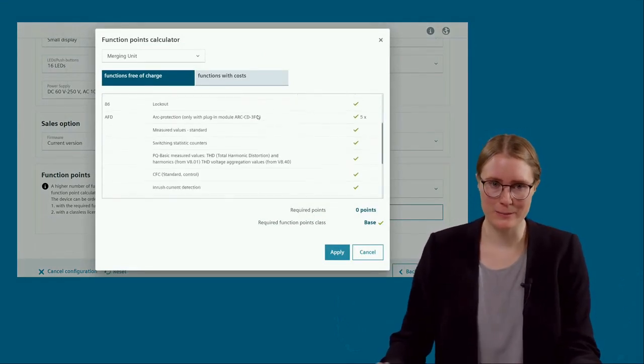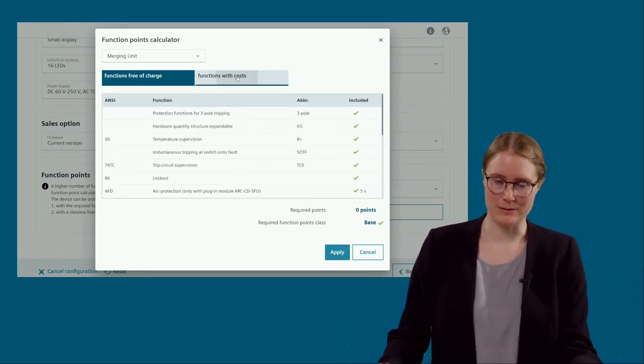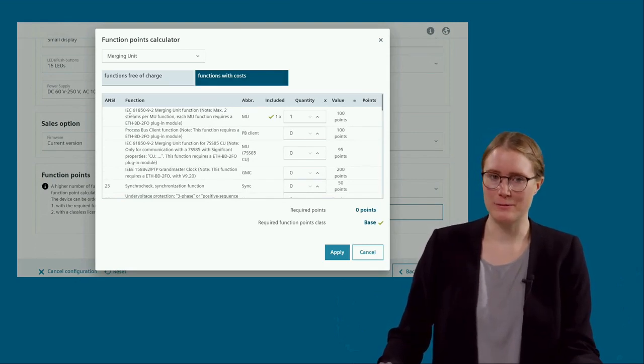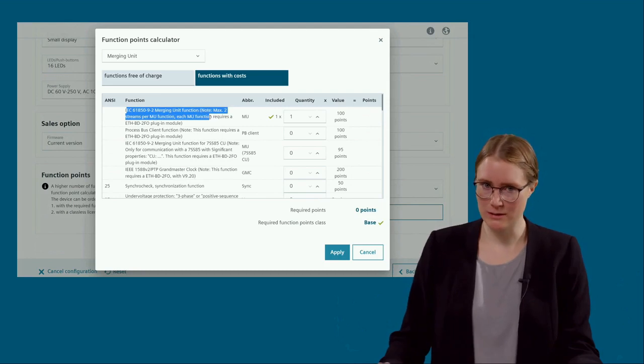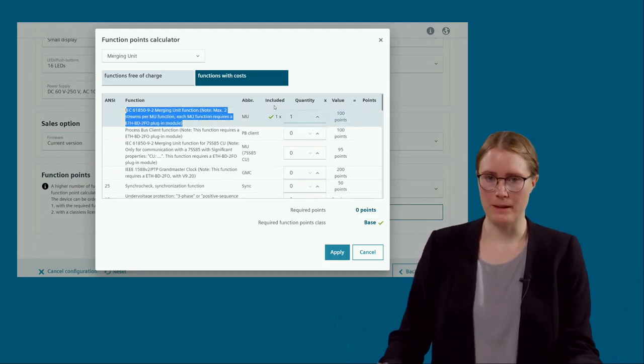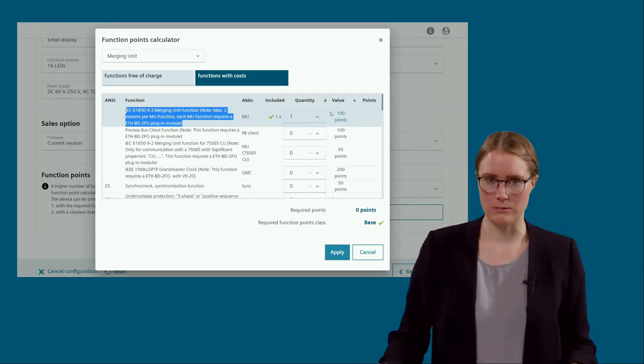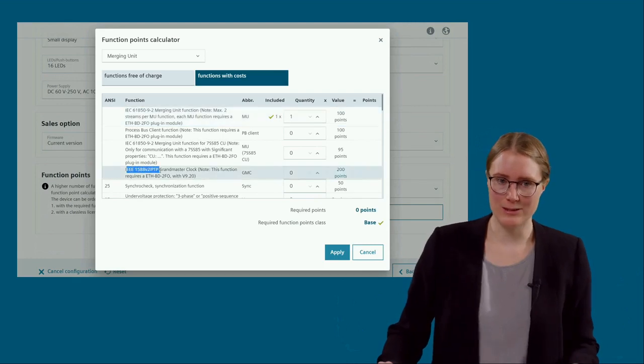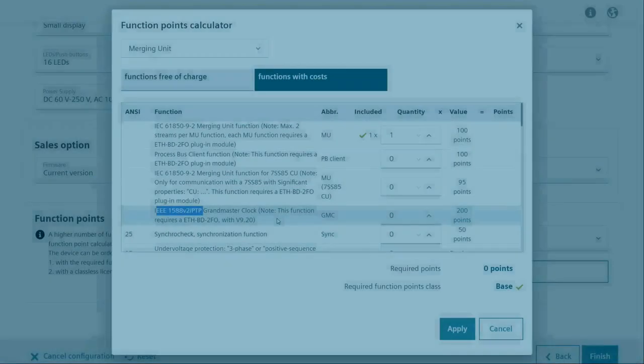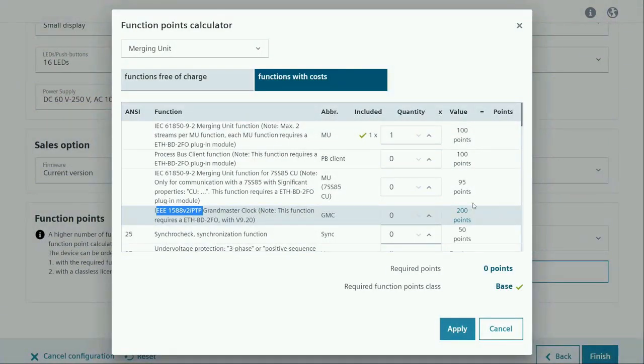Okay. Here there is not so much to show in the free of charge section. We jump directly to the function with costs. And here I want to start right with the first point. As you can read, the IEC 61850-9-2 merging unit functionality is already included one time in the 6MU85. So here we also don't need to pay function points for the communication with the central unit. Maybe also worth mentioning, the IEEE 1588 Grandmaster clock can be activated in the merging unit as well, but in this case it costs 200 function points. And we actually recommend activating this functionality in the central unit and not in the merging unit, but it would be possible.